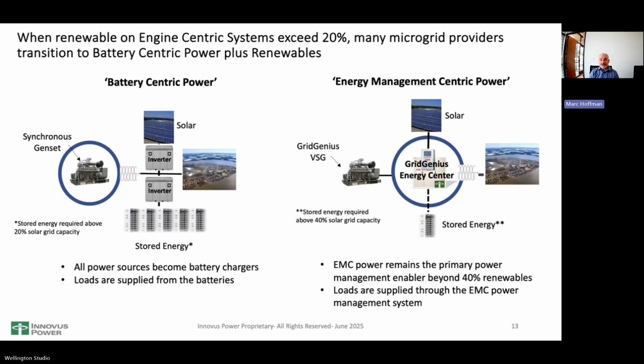So again, it's a solution that works, and there are certain scenarios where it's a better solution than, say, one where we store energy in the system just to keep the grid stable, with a certain amount of stored energy above 30 or 40% capacity to better harvest the solar and wind power that's very spiky. You'll see a case example of that. But also, if we want to do extended engine-off operations, which on the surface sounds like the absolute way to go, and in many scenarios it is, many communities use the heat from the engines for heating. So there's a trade-off between how much engine-off operation we want versus the benefit of the heat they deliver.